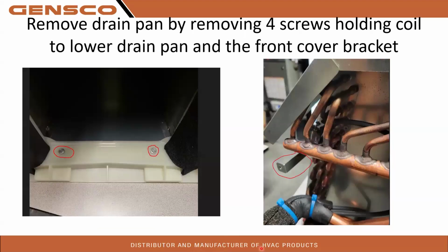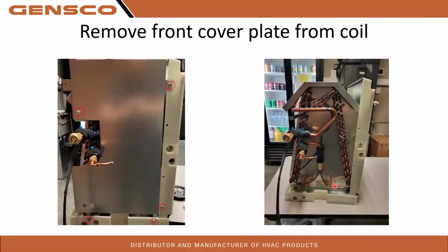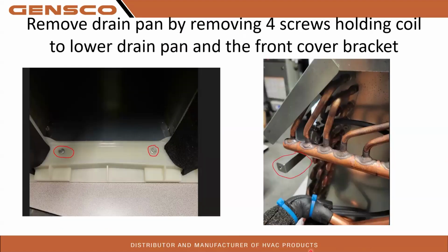In order to remove the lower drain pan, there's actually 2 screws in the back side of that coil going through the drain pan from the inside. And there's also 2 screws on the front. One's here and one's right there. In order to take this lower pan off, those screws will have to come out. If you're trying to take this pan off, this lower pan has to come off. So that's how you do that right there.